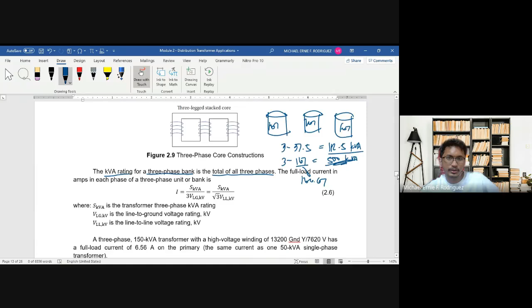Okay, so how do we get the full load current? Full load current again, for a three-phase. We have S divided by, similar to our AC circuits, where I equals S over 3 times your voltage line to neutral, right? Or I equals S over square root of 3 times your VLL, line to line.